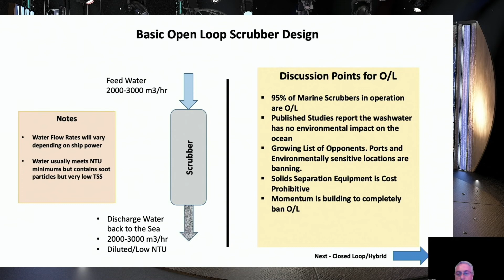The next slide shows, in comparison, the closed loop or hybrid system and its much lower amount of water. In open loop, you saw about 2,000 to 3,000 cubic meters per hour for this fictitious installation used as an example. In closed loop, you only see about 2.5 to 5 cubic meters per hour — an incredible difference between open loop and closed loop.